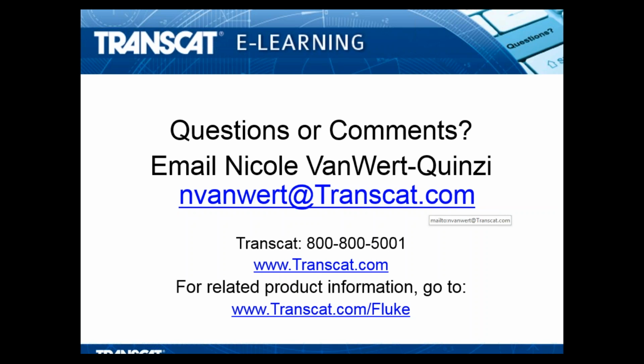That's a good question, because one thing I'd like to emphasize a bit more is that with the 754 it just changes the set points on a timer, so you do want to be careful about setting that delay.